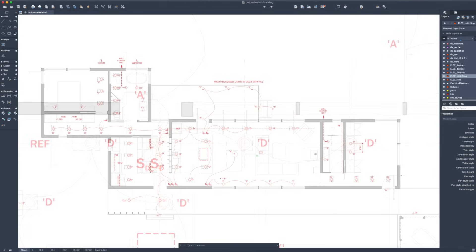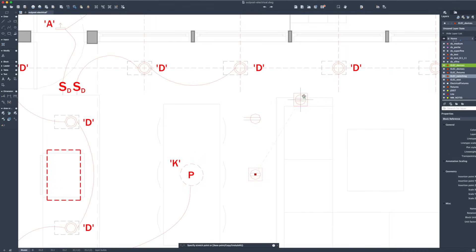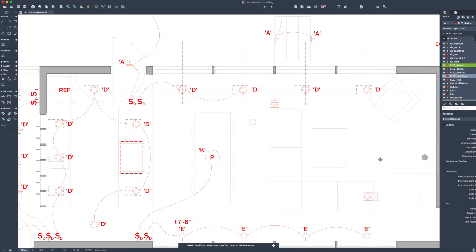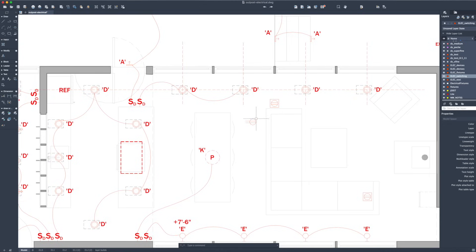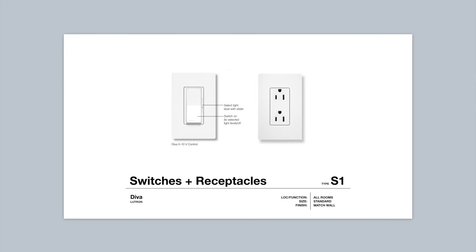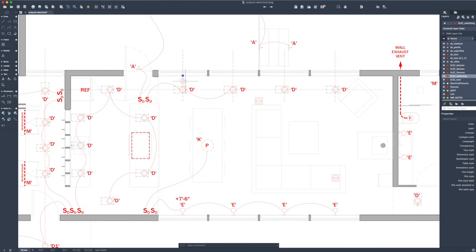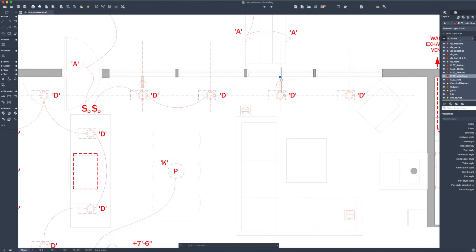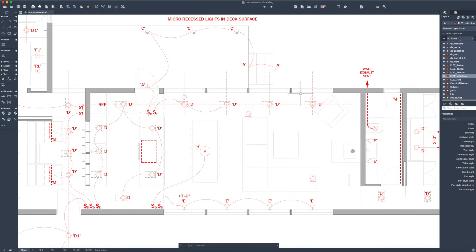The next step is to come and place some outlets. We have floor outlets in here — we know we want a floor outlet by the edge of this couch because we're going to have some task lighting for reading, and probably one at the other end of the couch as well. I'd still like to line things up where possible so if this furniture were removed in the future, it wouldn't look completely out of place. For wall receptacles — just like the lighting — I like to align them with architectural elements. The code dictates where we place our receptacles: we have to be within six feet of a receptacle. We have 12-foot center-to-center spacing here. We can space it to the center line of this end window and use this outlet to still be within six feet. As long as this outlet is within 18 inches of the wall, it still counts as a wall outlet.